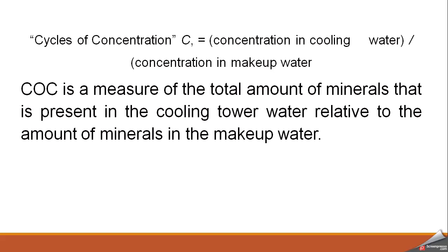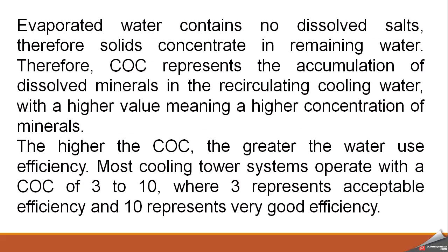So basically we take the ratio of the total dissolved solids or minerals present in the cooling tower water and the total dissolved solids or minerals present in the makeup water. You can say the minerals present in the cooling tower water are equal to the minerals present in the blow down water. So we can also use the ratio of the minerals present in the blow down water to the minerals present in the makeup water.